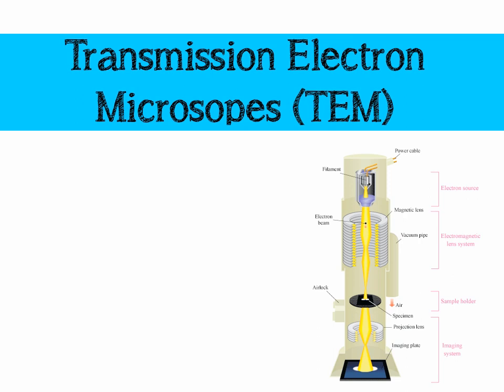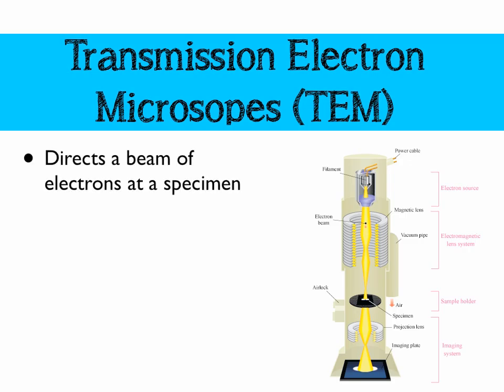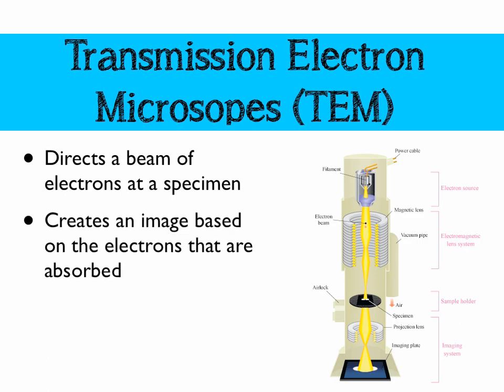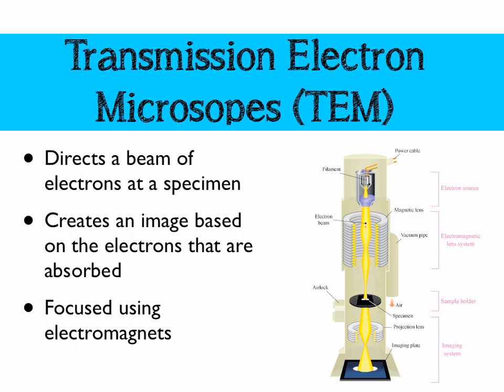The third and final type, and the second electron microscope, is the transmission electron microscope, or TEM. Again, we've got an electron beam being focused with a magnetic lens. This time, our electrons are going to pass through the specimen and onto an imaging plate, which is read by a computer. So, again, a beam of electrons is directed at a specimen and it creates an image based on the electrons that are absorbed — not the electrons reflected back like the SEM. Focusing is taken care of using electromagnets.